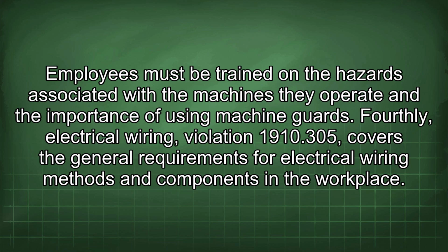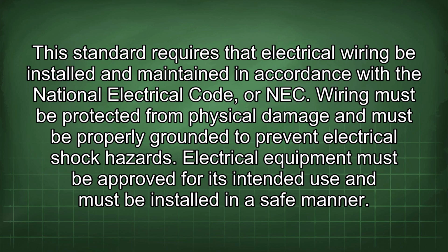Fourthly, electrical wiring. Violation 1910.305 covers the general requirements for electrical wiring methods and components in the workplace. This standard requires that electrical wiring be installed and maintained in accordance with the National Electrical Code, or NEC. Wiring must be protected from physical damage and must be properly grounded to prevent electrical shock hazards. Electrical equipment must be approved for its intended use and must be installed in a safe manner.